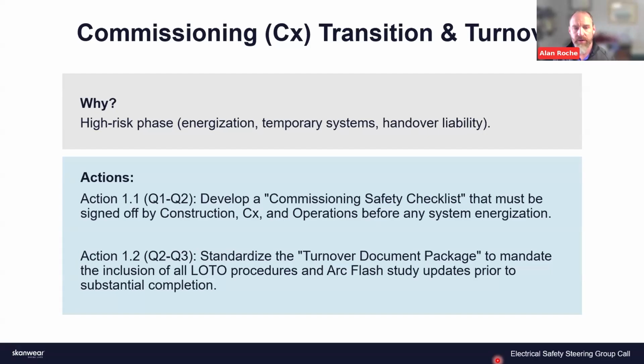Incomplete isolation procedures can create safety exposure. Another group will talk about lockout tagout after this. Load imbalance, grounding issues, equipment misconfiguration - can't tell you how many times we've popped the breaker because somebody put the wrong number into a load bank controller. So this safe test environment, prior to energization, now becomes a significant issue, where we've got human safety, equipment, and the actual mission, the production schedule of the data center you're delivering.